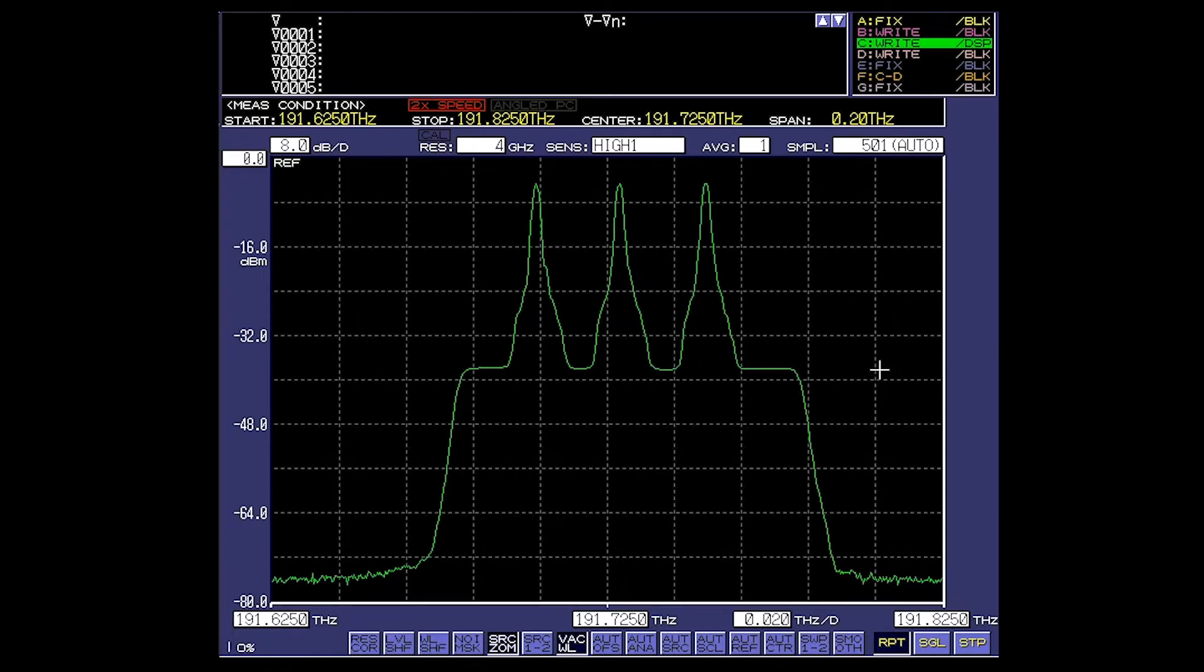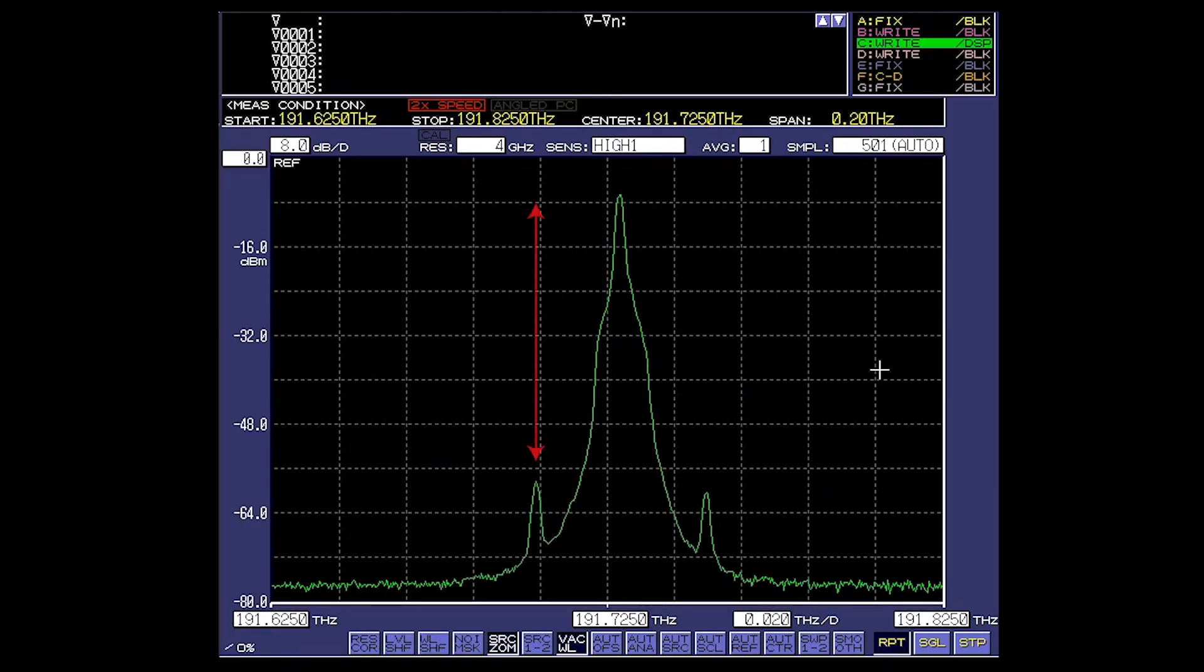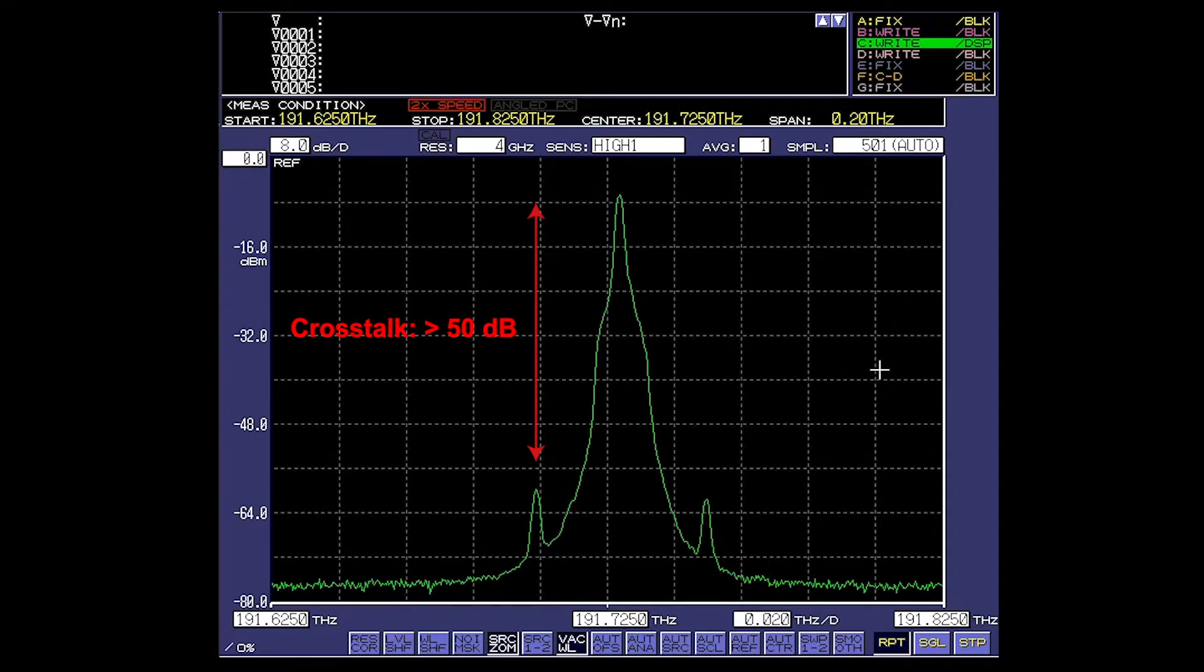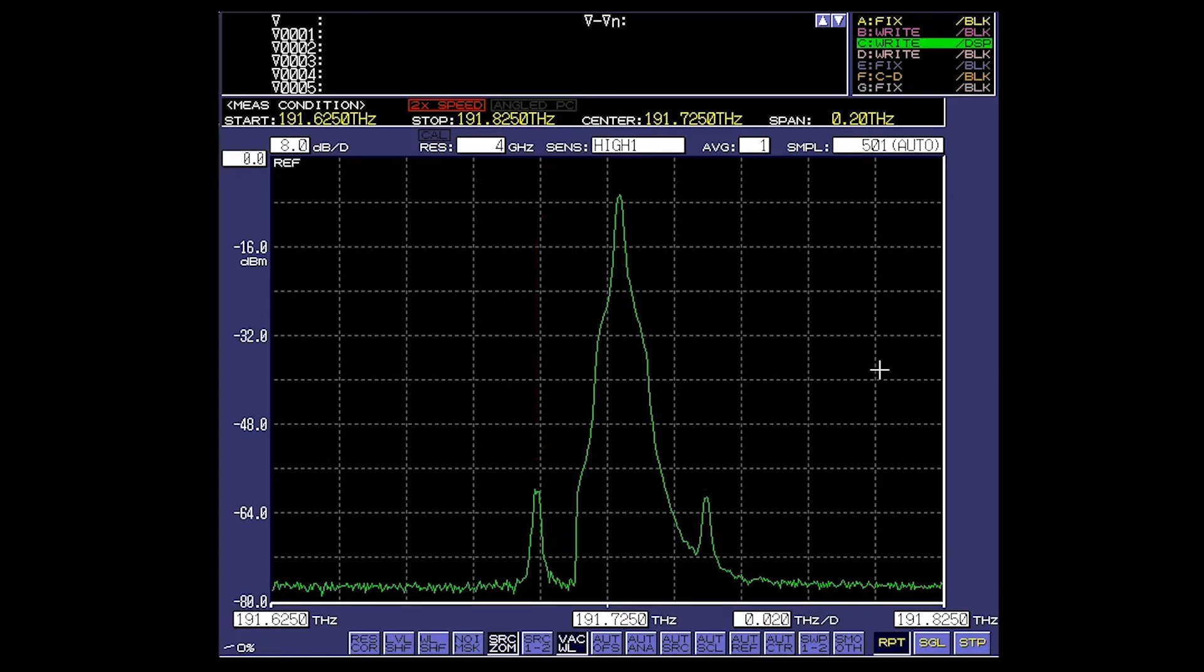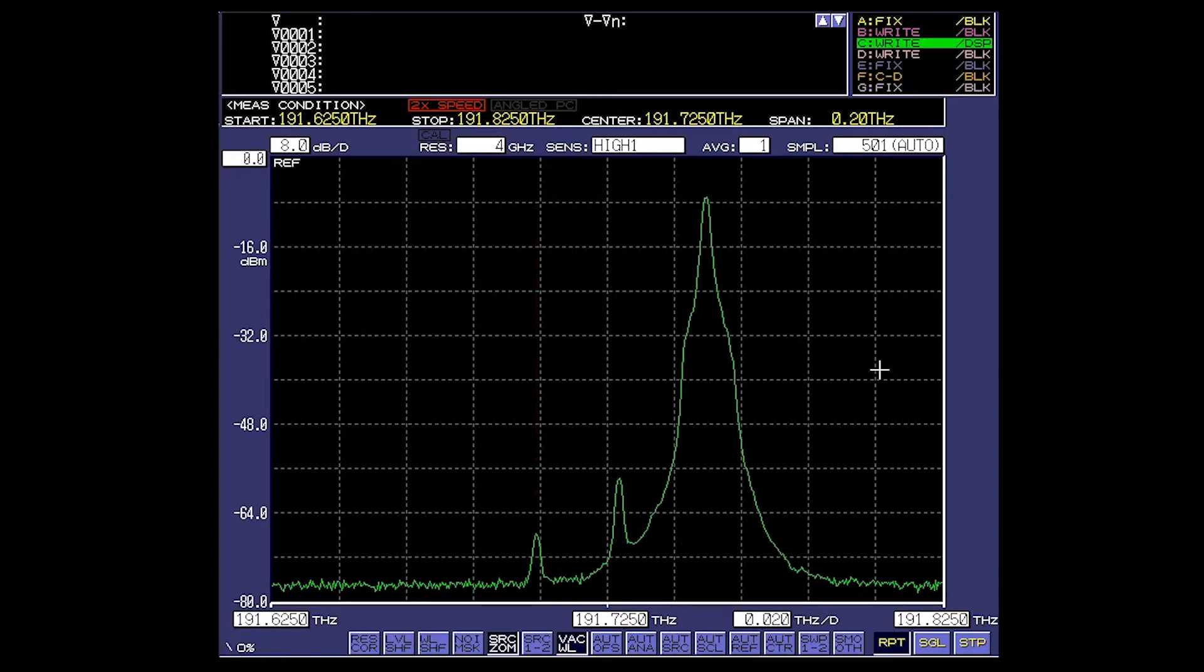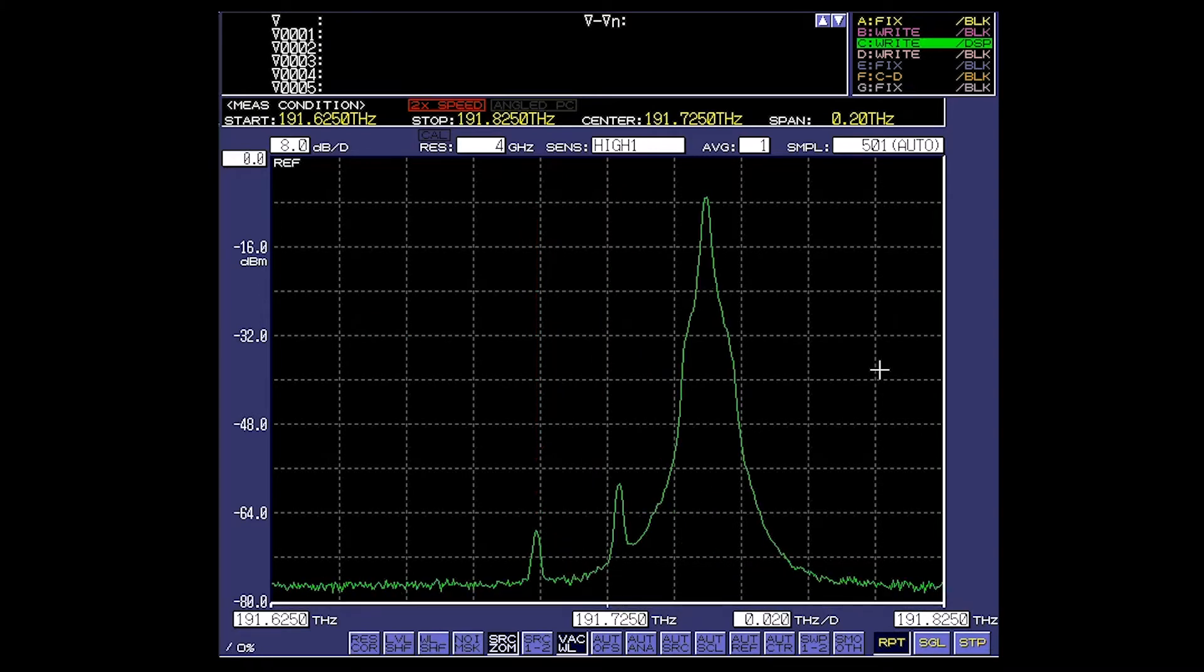With peak search functionality and a crosstalk attenuation over 50 dB, the OTF-980 is here to match the needs for 100 and 400 G-transmission testing, ASE noise filtering, and next-generation optical cross-connects.